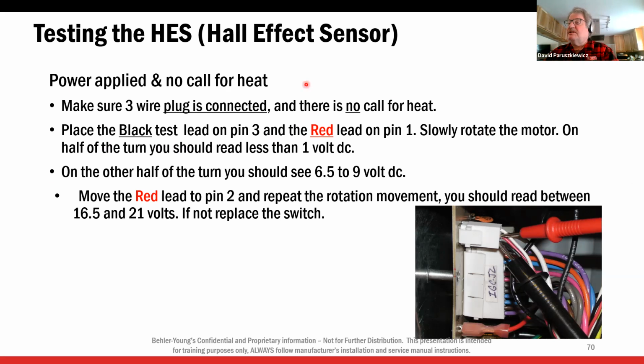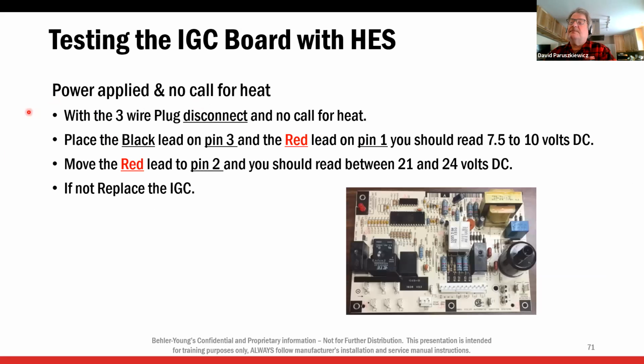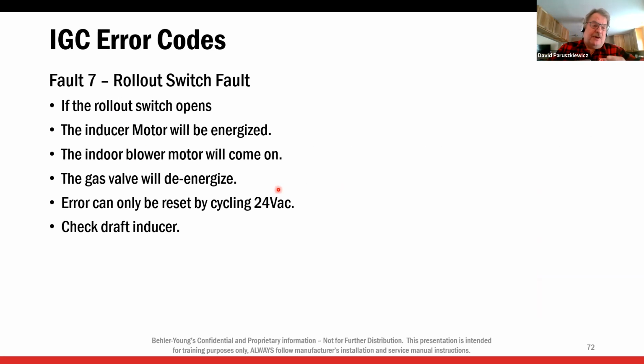All right, and if you look through here, place the black test lead on pin 3 and the red lead on pin 1, and slowly rotate the motor. You should get about 1 volt DC. So it's a pretty simple test. Power applied, no call for heat. And then the second half of the test. Instead of a pressure switch telling it it's on and off, it's generating a DC voltage and telling the board that yes, the motor's running.